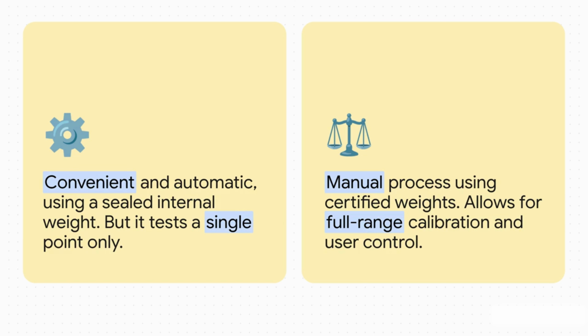But that weight usually isn't certified, and it only tests one specific point. Then you've got external calibration. This is the gold standard. A trained technician uses a special set of certified weights to test the balance across its entire range. It's manual, for sure, but it gives you a much more complete picture of its accuracy.